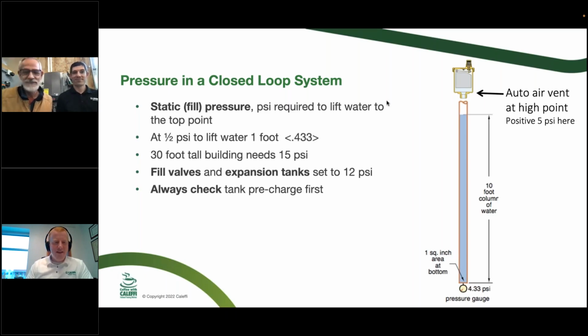No, I think you hit the nail on the head. I mean, especially for the contractors in the room, you got that bullet point at the bottom. Always check your tank pre-charge. I don't care who the manufacturer is. You've got to check them beforehand. And even when you start comparing tanks to fill valves, maybe your fill valve's set to 15, your tank's set to 12, or vice versa. We're seeing a lot of these European expansion tanks that are coming in pre-charged at 15 for some of the smaller applications. You just got to make sure that it's got the right charge in it for sure.